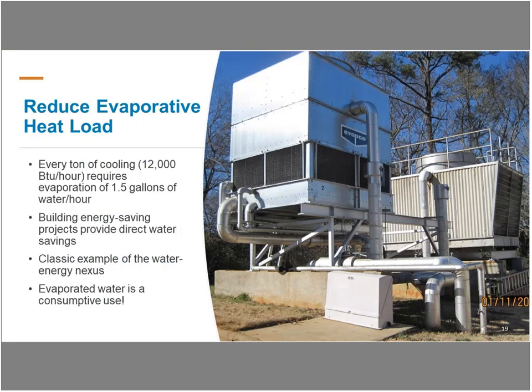So first I'll talk about reducing evaporative heat load. Evaporation is really the primary function of the cooling tower and is how most of the heat is carried away from the system. Based on general thermodynamic properties of water, about 1.5 gallons of water are needed per hour for every ton of cooling. And this number is fixed. Since we want the cooling to occur, evaporation is generally not the focus of water efficiency. However, anything we can do to make the chiller plant more energy efficient will help lower your cooling load and thereby also reduce the amount of water needed for evaporation.